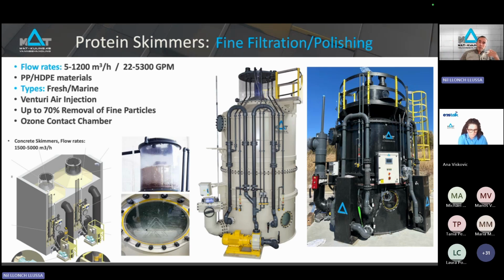So it's moving in both different directions, and the bubbles themselves create the foam by interaction with the particles that you have in the water. These fine particles are trapped with the bubbles, with this foam that overflows from the top of the cone, and you create this dirty foam, as you can see in this picture, which is discharged, therefore cleaning your water.